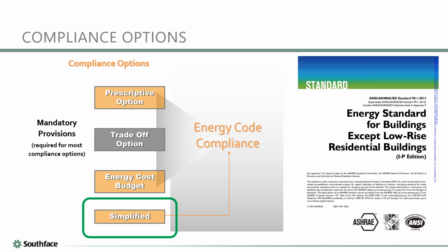So that's important to know, that if you want to go this simplified route, your building needs to meet sort of a list of requirements and qualify as, we'll just say, a simple building. You're also going to have to be permitted under the ASHRAE 90.1 standard. And in Georgia, starting in 2020, that'll be the ASHRAE 90.1 2013 standard. So this is something that a building would really want to do, because it takes a lot of complicated information that's in the mechanical section of the code, and it distills it down to a list of, let's just kind of wave our hands and say, 20 or so items that the building is going to have to do in order to show compliance.